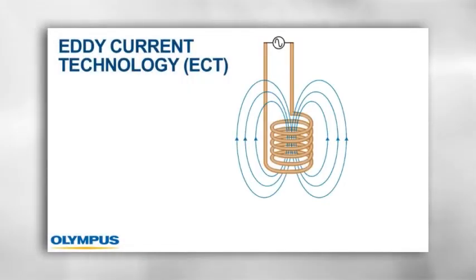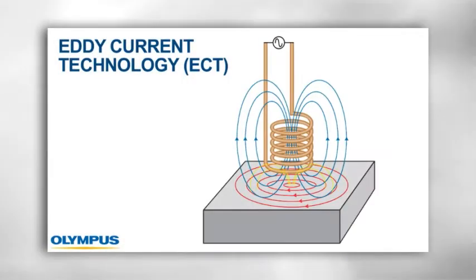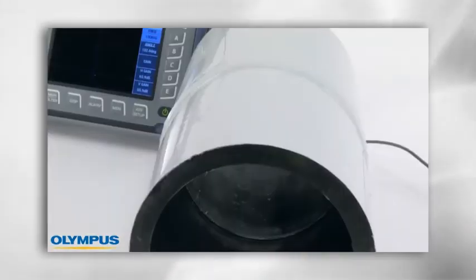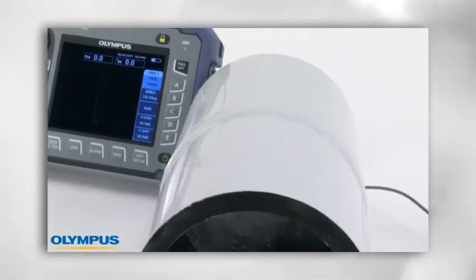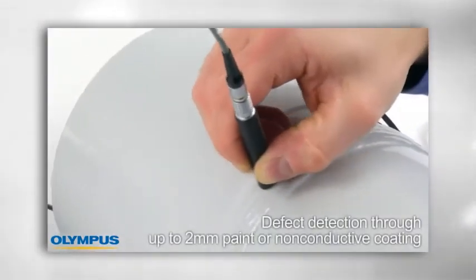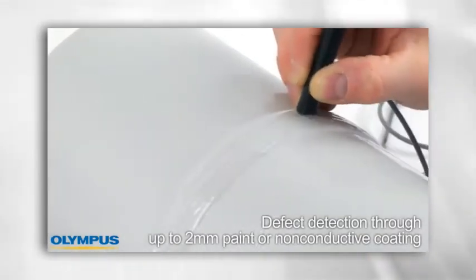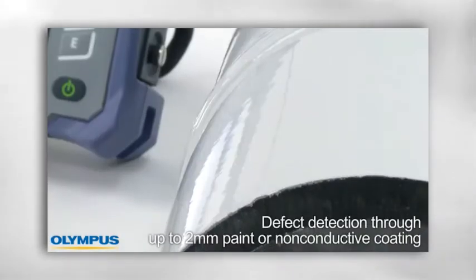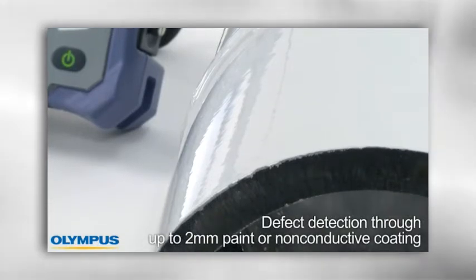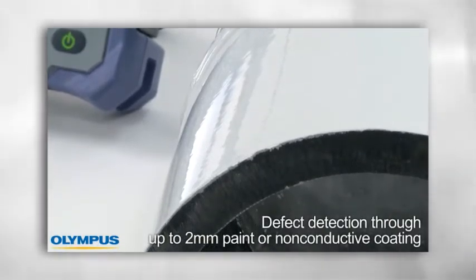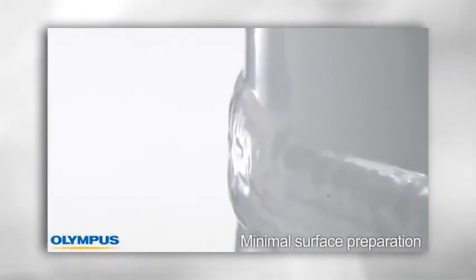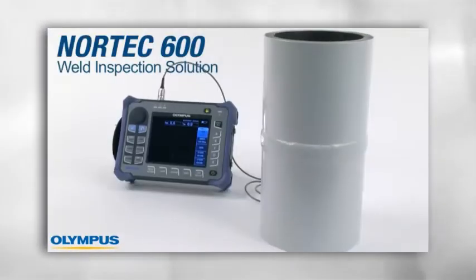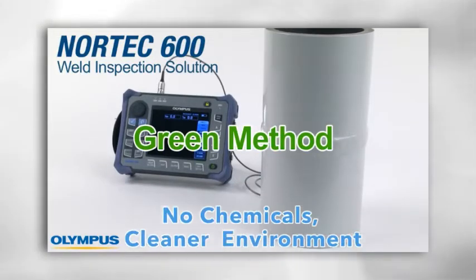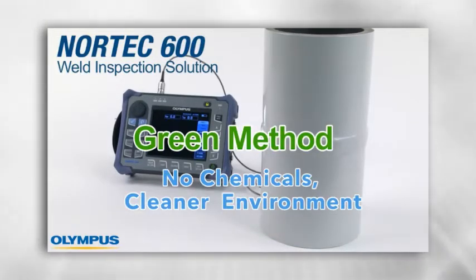Eddy current technology uses a magnetic field to couple the sensor to the part, so a certain distance between the probe and the part is permissible. That means the Nortec 600 weld inspection solution can detect defects through up to 2 mm of paint or non-conductive coatings. The ability to inspect through paint or coatings makes removing these layers unnecessary, and eddy current technology also requires minimal surface preparation. As no chemicals are involved in the process, the Nortec 600 weld inspection solution contributes to a cleaner environment.